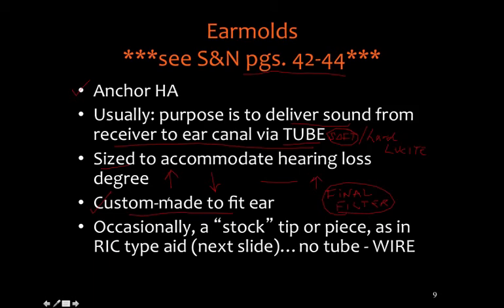It's also possible that the person doesn't get the hearing aid in their ear correctly. It's a custom-built product to the specific spaces of the outer ear, and if they don't get it in the ear exactly where it's supposed to be, it's possible for a person to just kind of jam it in there, but it's not going to be aligned correctly, and there's going to be some points of soreness. So I'll see a person come in, they complain, oh, my ear hurts. The hearing aid doesn't fit right, my ear hurts. And I look at it, and they don't have it aligned in their ear right, and there'll be some typical hot spots, sore spots, where they don't have it seated correctly. And that's now a question of education, of re-instructing them to get this into their ear correctly. But that's partially up to the user of the hearing aid to get it in there correctly.